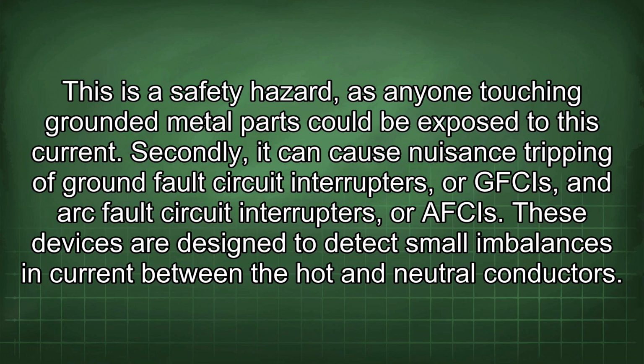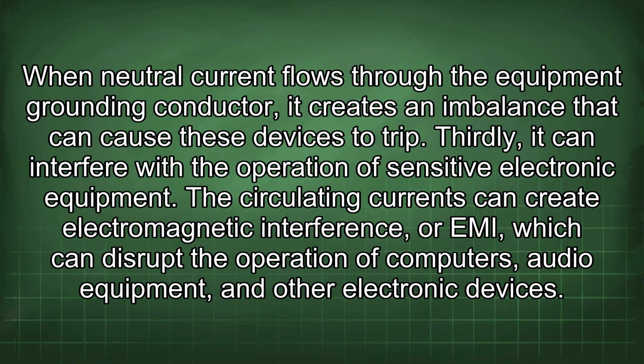Secondly, it can cause nuisance tripping of ground fault circuit interrupters, or GFCIs, and arc fault circuit interrupters, or AFCIs. These devices are designed to detect small imbalances in current between the hot and neutral conductors. When neutral current flows through the equipment grounding conductor, it creates an imbalance that can cause these devices to trip. Thirdly, it can interfere with the operation of sensitive electronic equipment. The circulating currents can create electromagnetic interference, or EMI, which can disrupt the operation of computers, audio equipment, and other electronic devices.